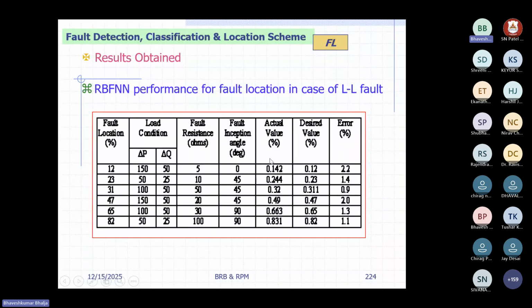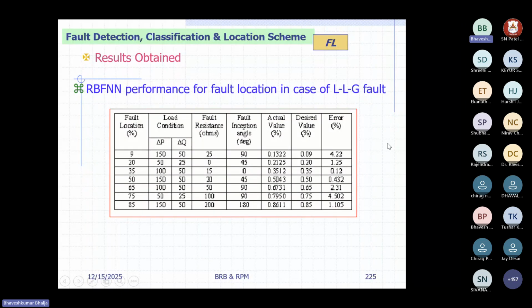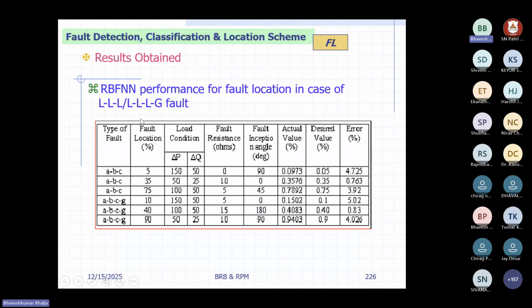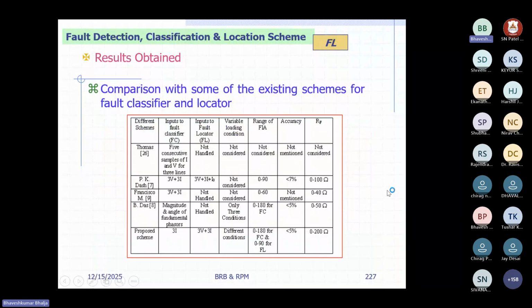Similarly, for line to line fault, you can calculate the percentage error, and for all cases you can see it is below, let's say, 5%. Double line to ground fault also you can see, and triple line or triple line to ground fault also, it may reach up to close to 5%, right? And why does it reach 5%? Because I have taken a minimum number of features. If I increase the features, then this error may reduce, right? But again, you have to see whether, by increasing the features, your neural network or the AI ML algorithm becomes overloaded, right? So that optimization you need to do.